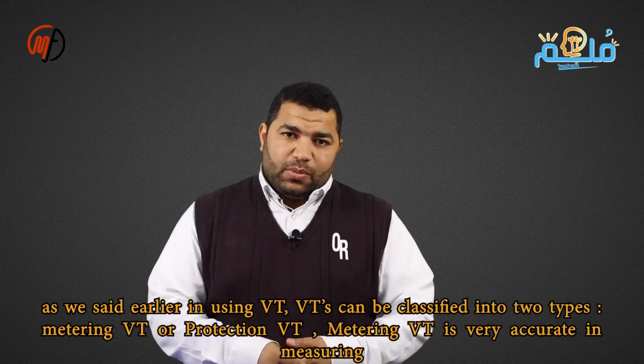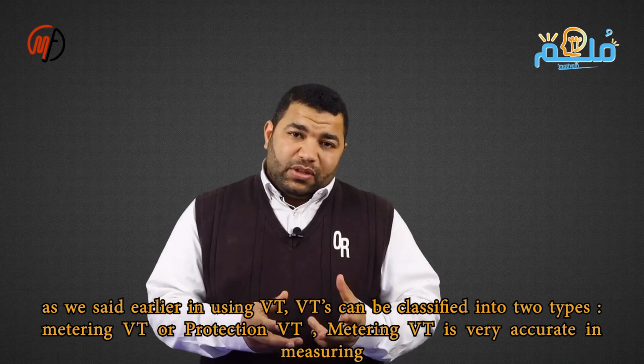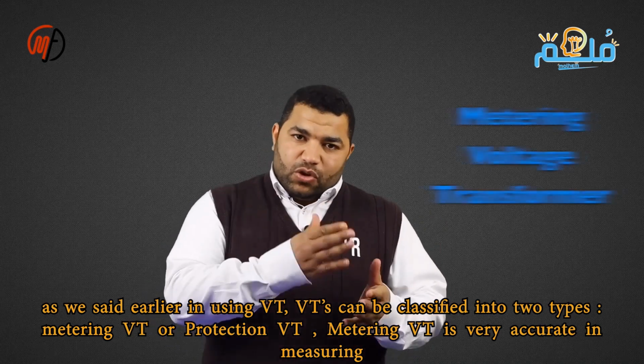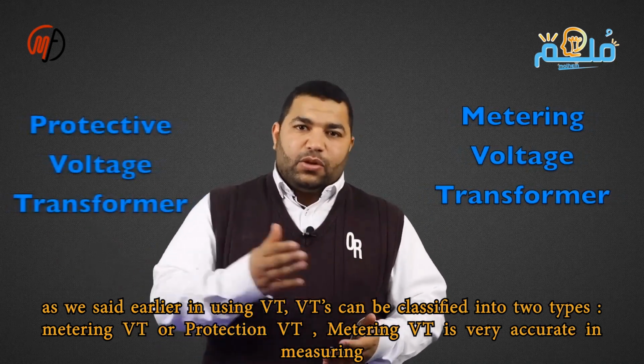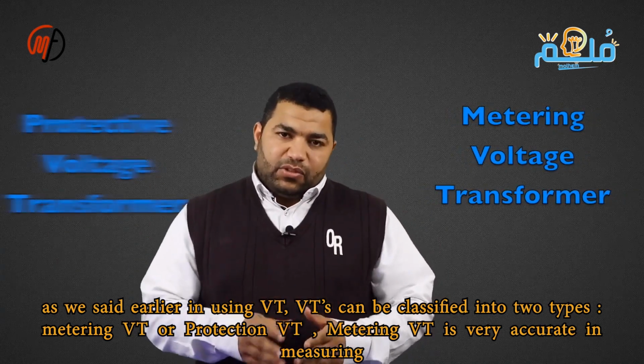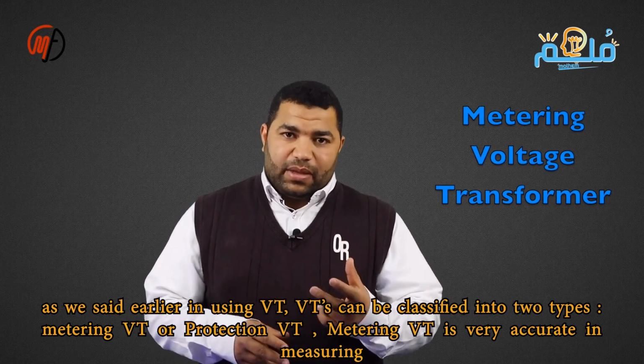Voltage transformers are split into metering and protective types. Metering types are class 0.5 with plus or minus 0.5% error. Protective types marked P are class 3P with plus or minus 3% error. Higher class values mean more error.